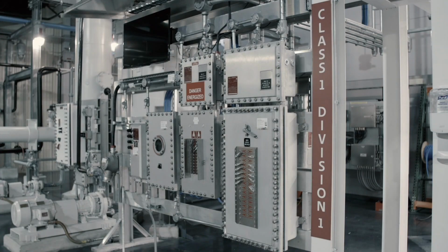When designing a facility, there is a team that looks at risk, and the electrical member of the team plans their equipment not to be in the hazardous location. For example, if you install a floodlight in an unclassified location, it could shine into the division location. Using unlisted equipment can save an initial cost and maintenance, but sometimes using HAZLOC listed equipment is unavoidable.